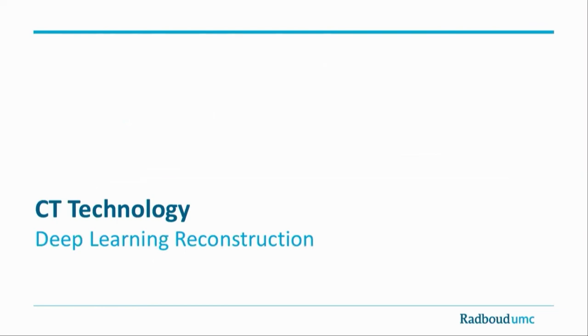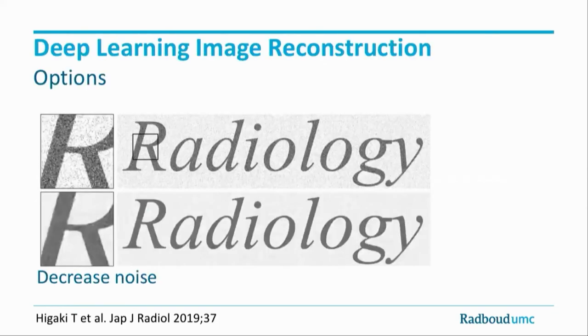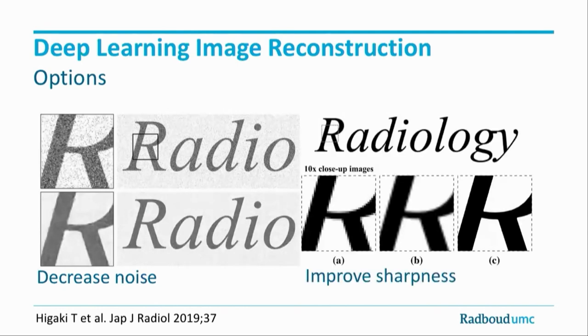The solution is deep learning reconstruction. With deep learning reconstruction, you can choose to decrease image noise, but you can also use it to improve sharpness. Here's an example where you can see the pixelation and classic interpolation versus the high-resolution deep learning reconstruction — really good resolution from a low-resolution data set.